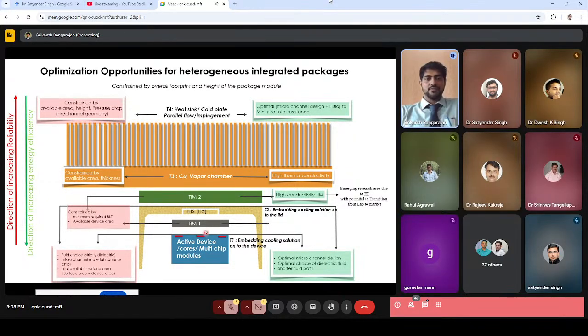Then you have the first thermal interface material, and then an integrated heat spreader or lid. This lid, the TIM1, and the active silicon device together are called the chip package. The chip package is then attached to a heat sink through another thermal interface material, followed by a copper heat spreader or vapor chamber on top, and then micro channels or air-cooled heat sinks that actually remove the heat.